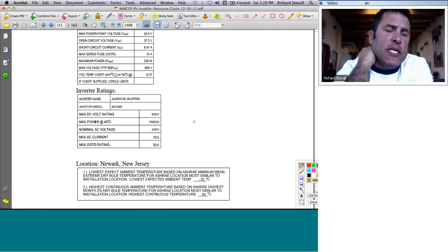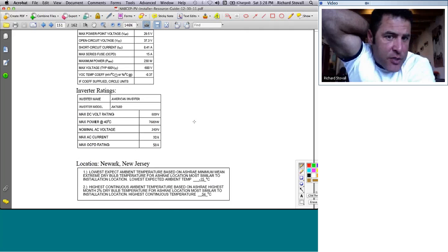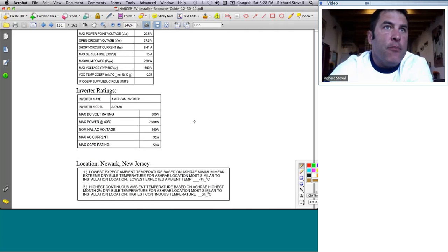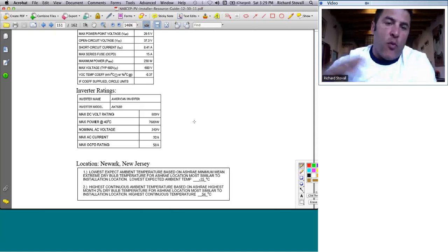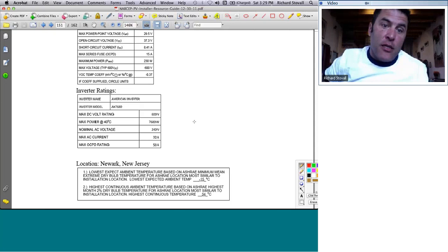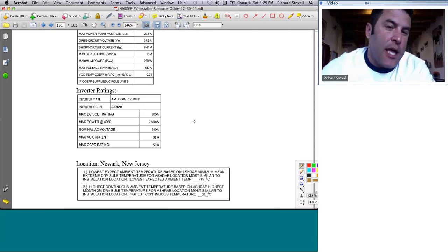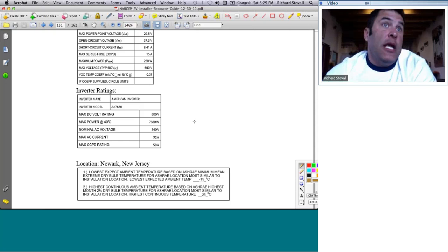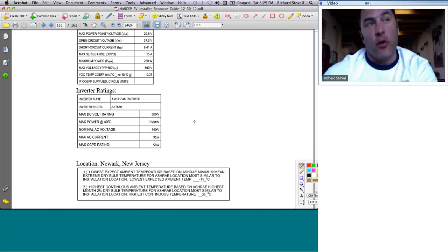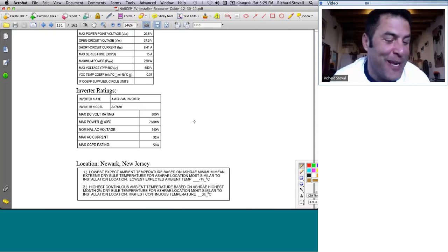When you're considering a design element like voltage drop, typically you'd design around a voltage drop percentage under the conditions that the system is operating at most of the time. While the inverter itself may have a wide voltage range, the system you're applying to it has a narrower range. So you wouldn't necessarily design a voltage drop calculation around the minimum input voltage of the inverter. If you wanted to be conservative, you would design around the minimum voltage production from your array. I'm just trying to guess where the 240 came from. Good guesses. I think you just made a mistake, though.